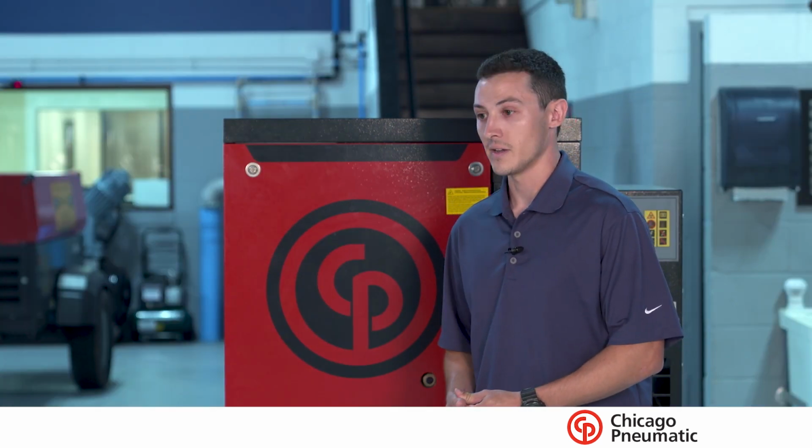Your compressor is going to be running a lot more often, cycling on and off, causing unnecessary wear and tear on your compressor because that air is not getting used for your tools. If you suspect that your compressor is cycling on and off more frequently than it should and you don't think that you're using tools, a good way is maybe after hours, leave your compressor on. If it's cycling on and off and no one's using any air tools, that's a good giveaway that there's an air leak, that air is going somewhere. If you suspect it's in an area, you can use a little soap bubble solution and see if you get any bubbles forming. You could also use your ears, just listen to see if you hear any hissing.